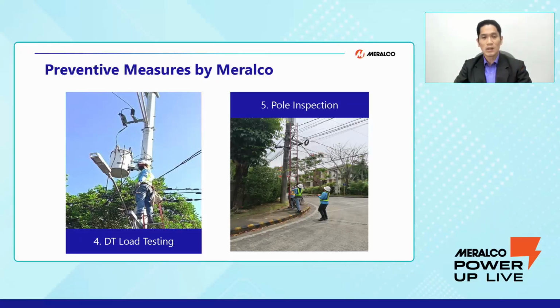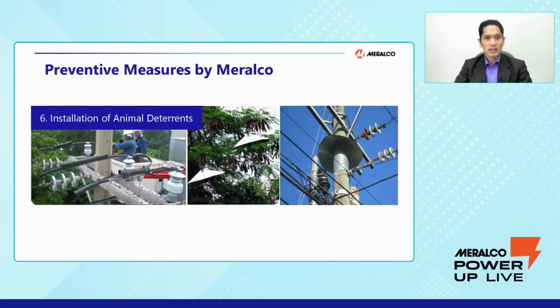And for the pole inspection, Meralco conducts this to check for any foreign objects, abnormalities, or any defects that may be found in our poles, and that are already subject for replacement or correction. And installation of animal deterrents. So we have these bird spikes in the left picture. Our cross arm, where the insulators are placed, is given spikes so that the birds will not go there, which might result in a line to ground fault. And these cones in the middle and right pictures are the snake cones, to prevent snakes from coming up to our distribution lines and facilities.